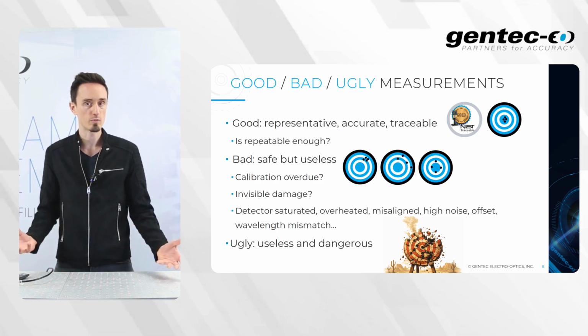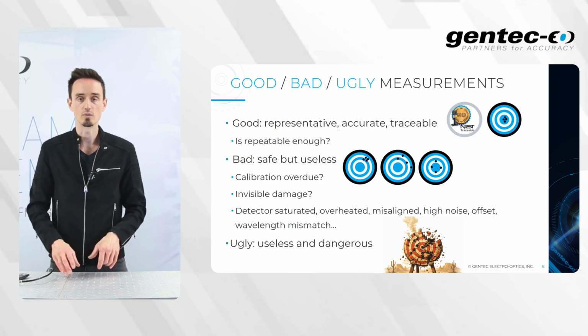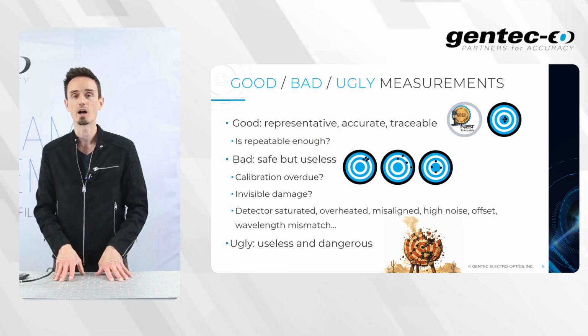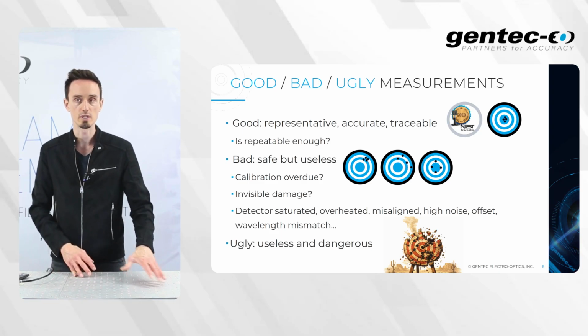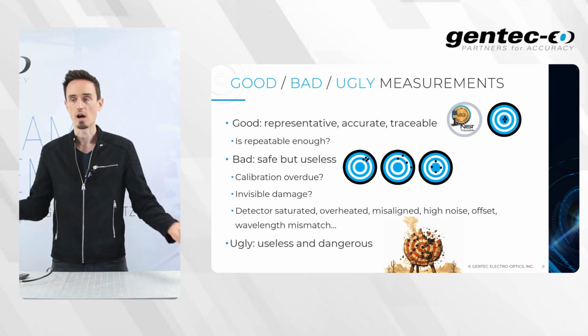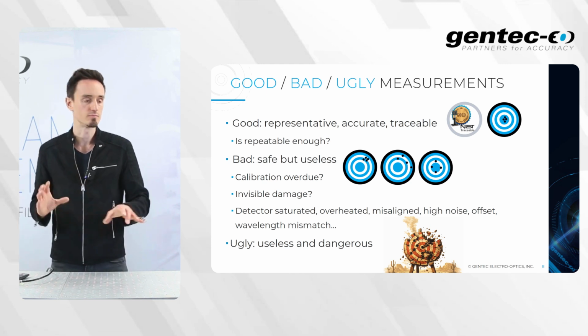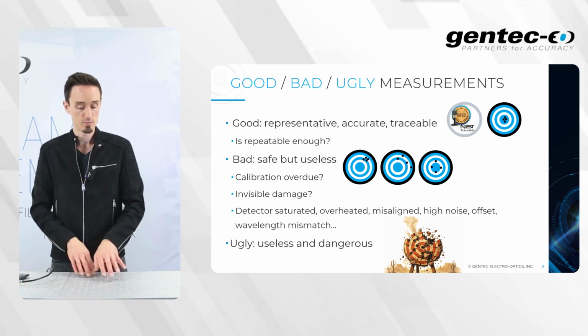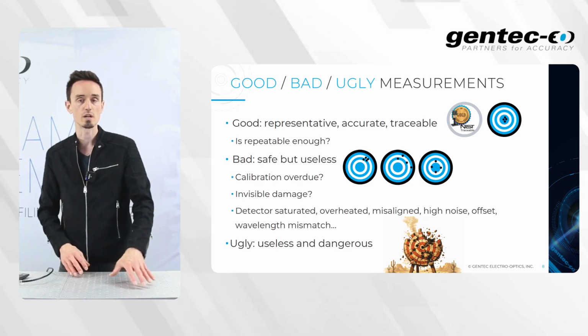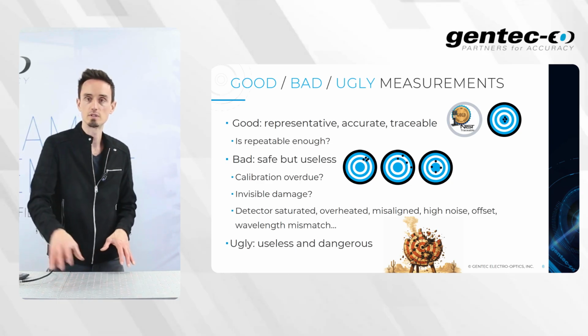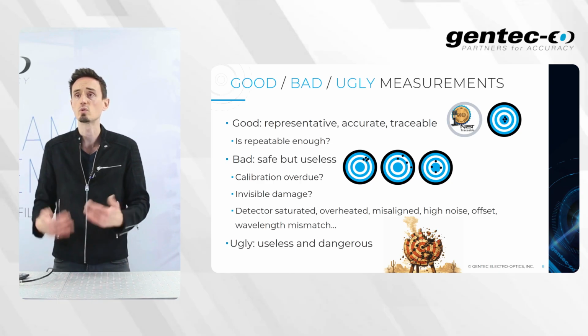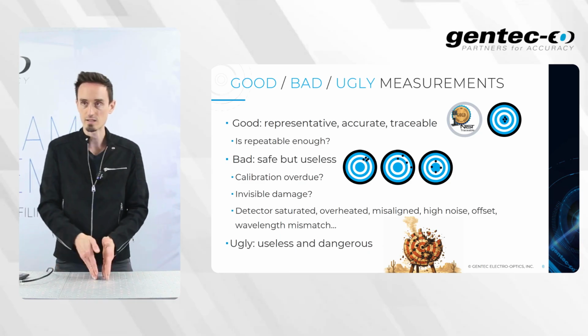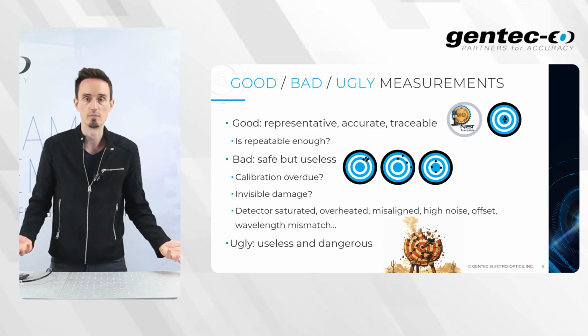There is some invisible damage. The detector could be saturated, overheated, misaligned. The signal to noise ratio could be bad. They could have some offsets resulting from bad zeroing procedures and so on. Potentially the wavelength of the laser is not properly paired with the capabilities of the detector, resulting in some offsets. As you can see on those targets, it is not centered, it is spread out, it is not a good measurement.